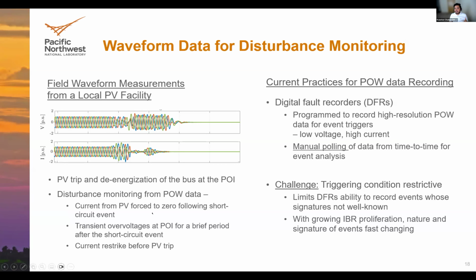You can see that the current from the PV was forced to zero quickly after a short circuit event. Then we see transient overvoltages in the voltages, and there was also a restrike in the current that followed. These are all signatures that help us understand what caused the PV to trip, and what patterns we can learn from these events.